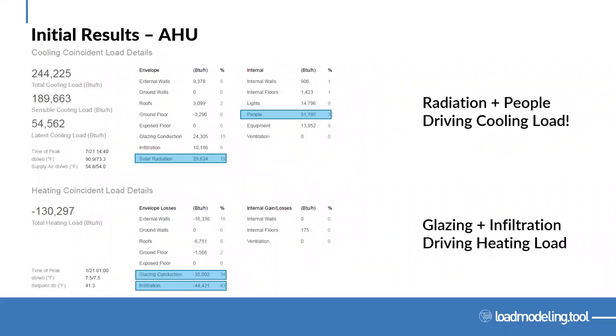Looking at the whole building now — at the AHU — to see what's driving the whole building load. I can see radiation is one thing, and then people is the other aspect driving the load in this project. Two elements I can look at to help reduce. For heating, glazing conduction and infiltration match between that one room and the whole building. In these initial results I can take what I've learned and start to modify my design or suggest modifications that will help reduce the load.